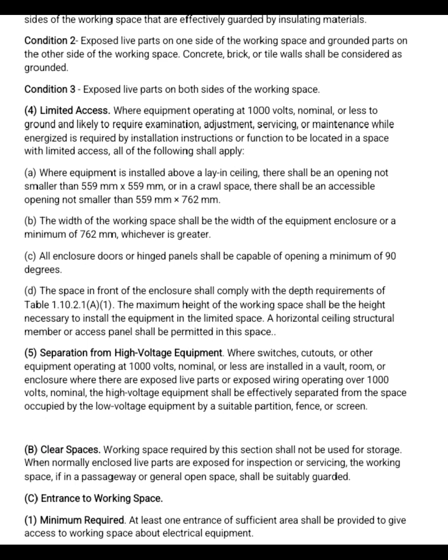C. Entrance to working space. Number 1. Minimum required. At least one entrance of sufficient area shall be provided to give access to the working space about electrical equipment. This indicates the limited access areas: if the electrical equipment is located in a tight or restricted space, like above a ceiling or in a crawl space, the following must be provided.